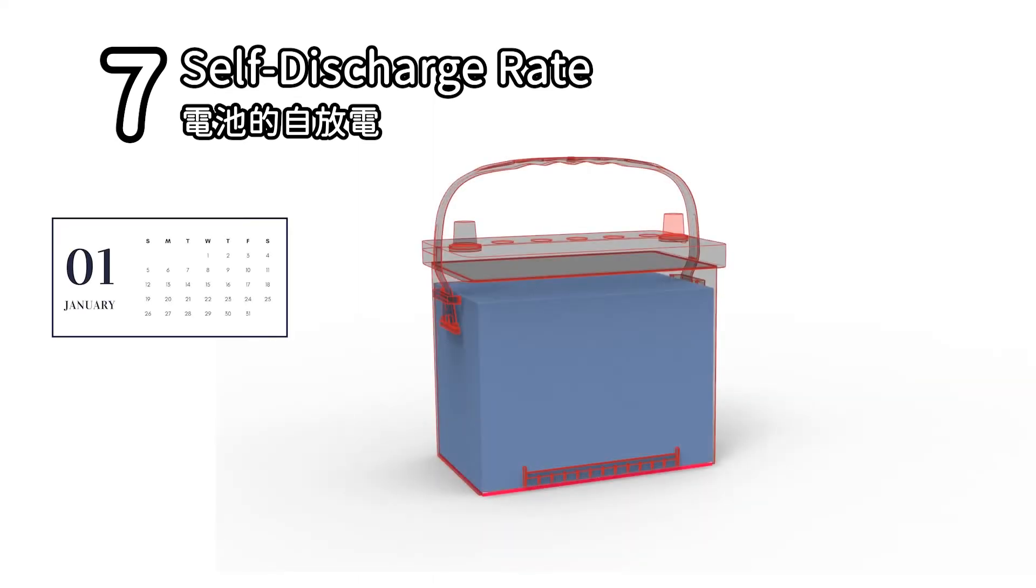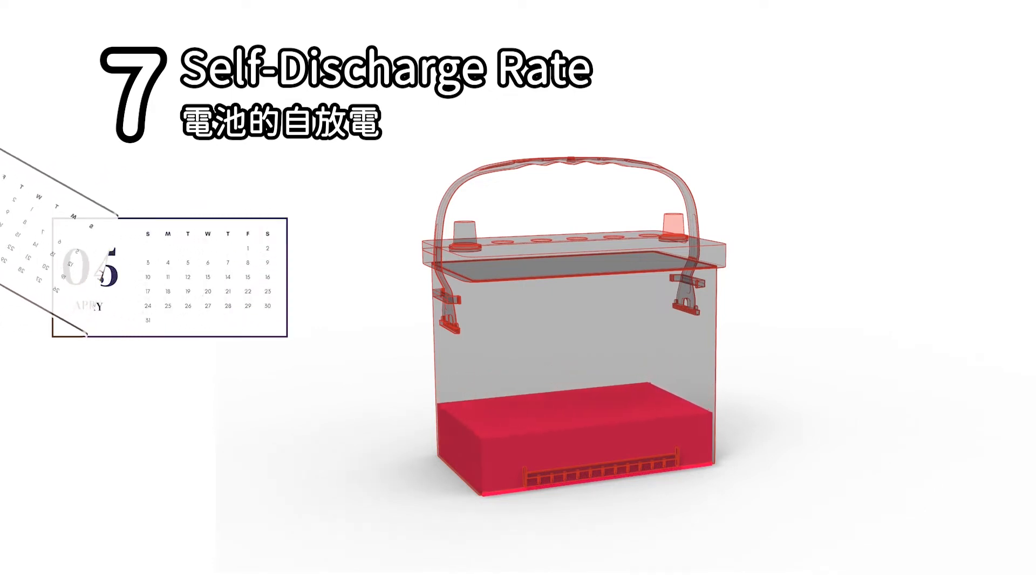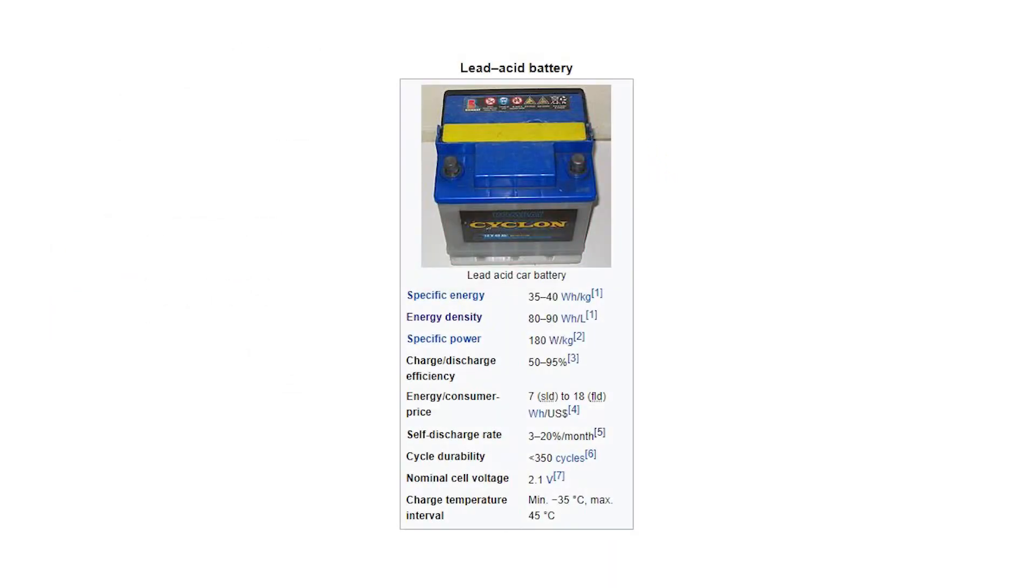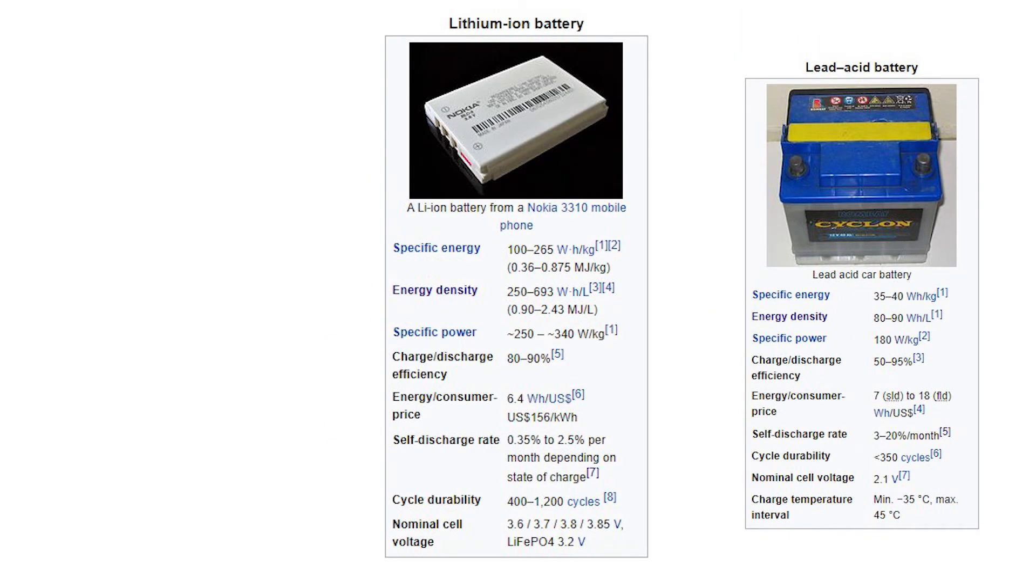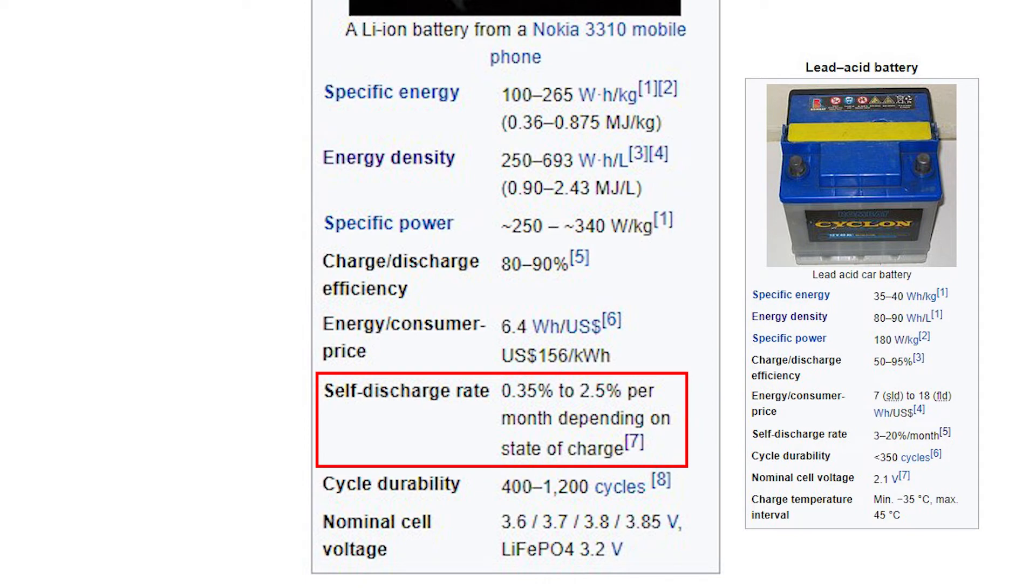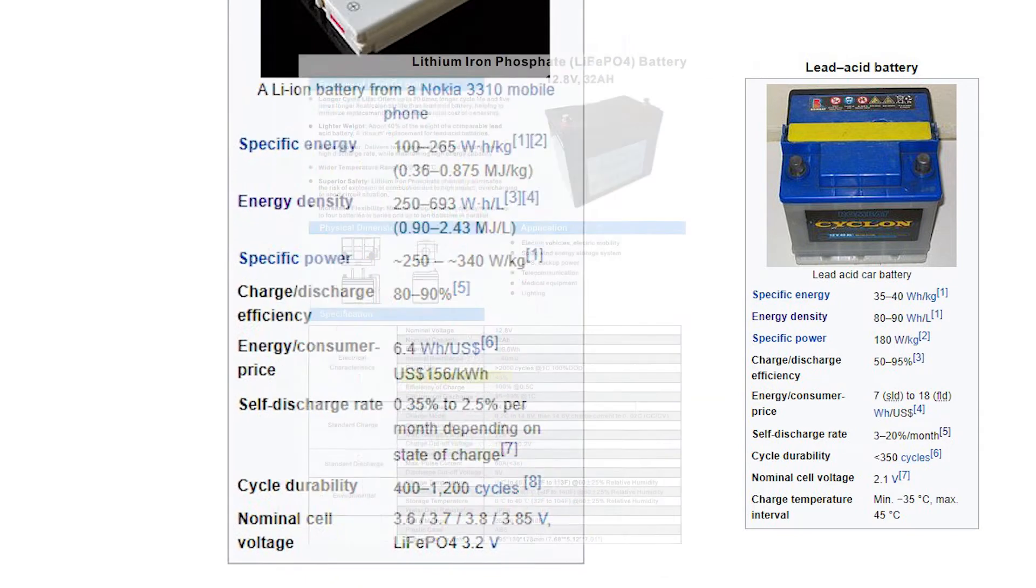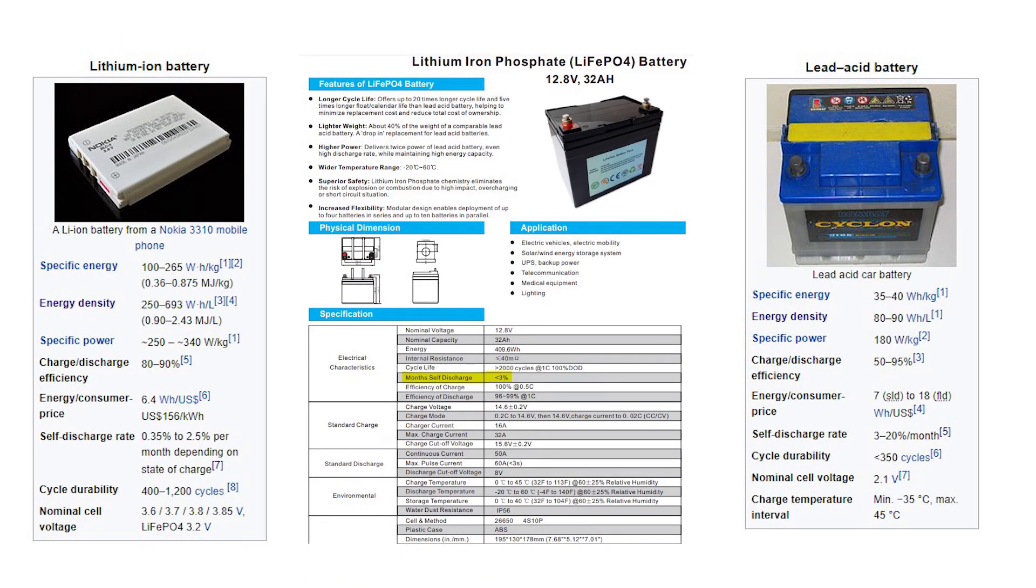7. Self-discharge of the battery. This is a phenomenon in batteries where internal chemical reactions reduce the charge stored in the battery. Even without any connection between the electrodes, the battery loses power. The rate of self-discharge will vary depending on battery type, ambient temperature, and other factors. According to the data, the self-discharge rate of lead-acid batteries is about 3-20% per month. Li-ion battery about 0.35-2.5%. LiFePO4 battery below 3%.